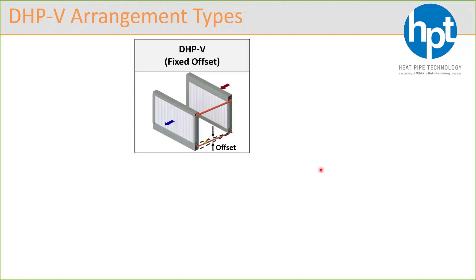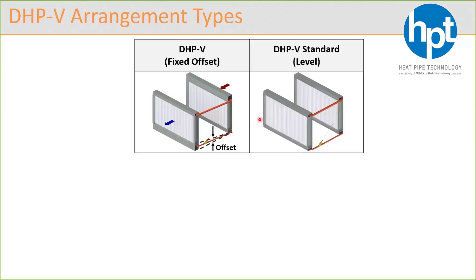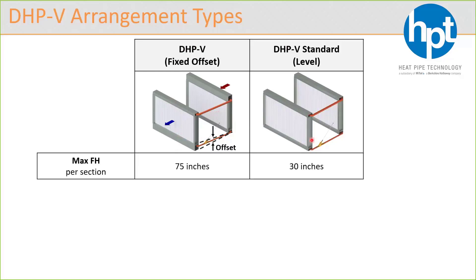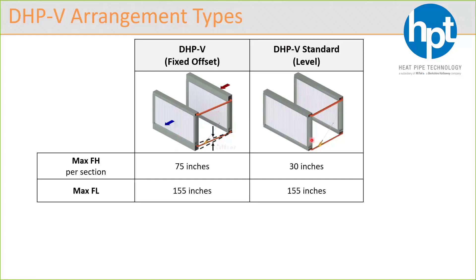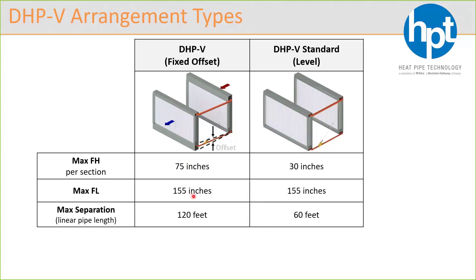For DHPV arrangements, we only have two types. One is the DHPV with a fixed offset — that's when you're elevating the reheat above the pre-cool. The other is the DHPV standard level arrangement. The max fin height for fixed offset is 75 inches versus 30 inches for level. Max fin length for pre-cool and reheat is 155 inches for both cases. Max separation is 120 feet for fixed offset and 60 feet for level, though in practice with DHPVs or wraparounds you're typically looking at 10 to 12 feet of separation.